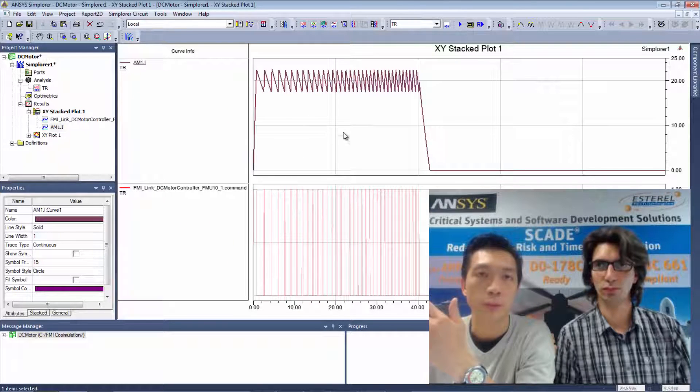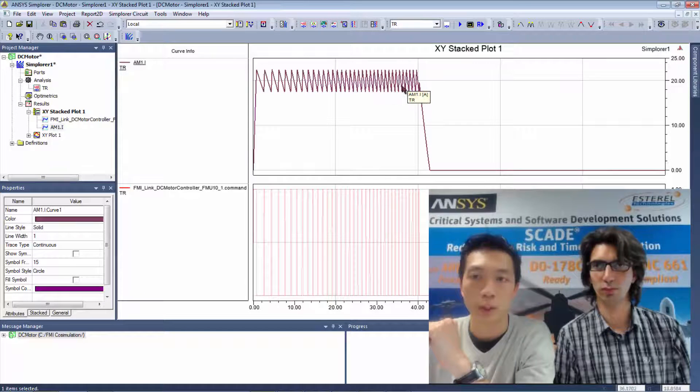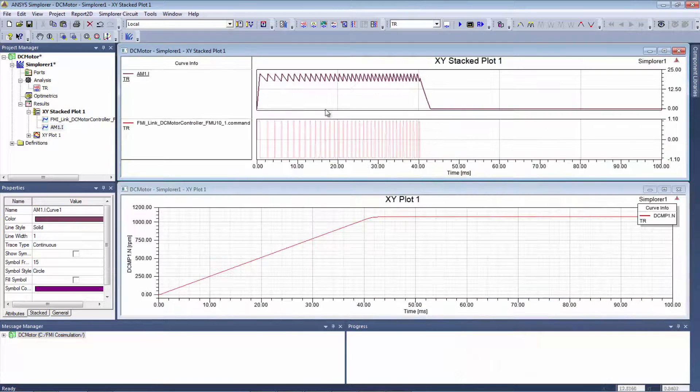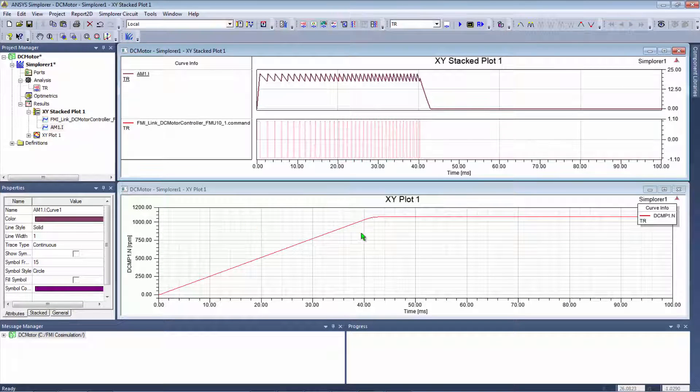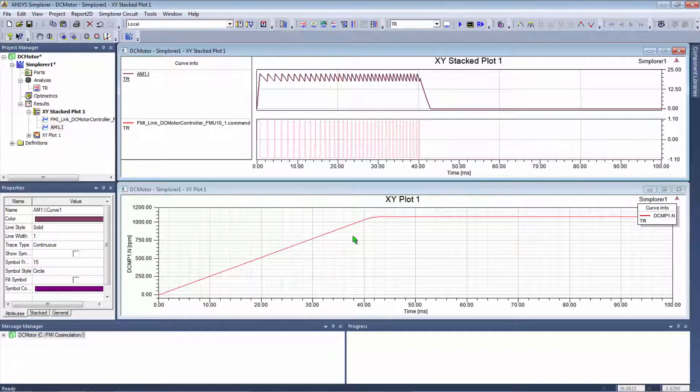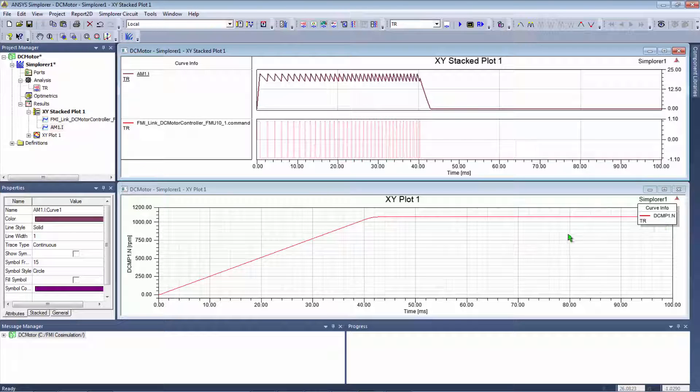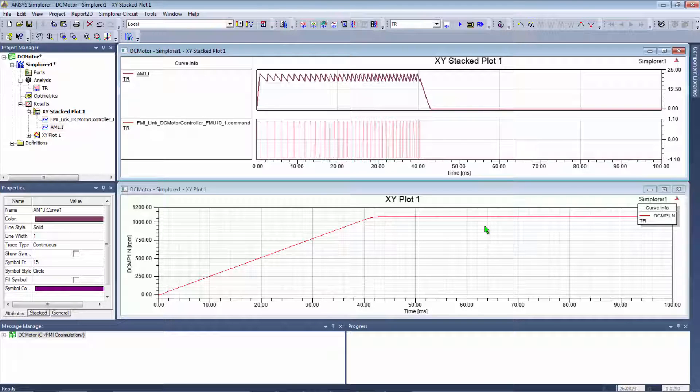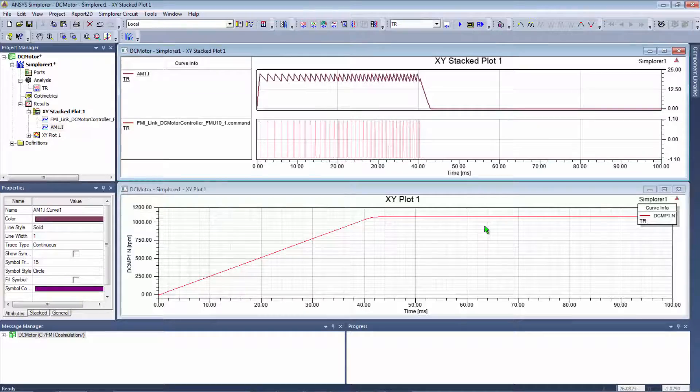And here we can see on the current waveform the hysteretic effect which is regulating the current here. And the regulation goes on until the regulation speed is reached. This is what you can observe here on the plot of the rotor speed of the machine. And this behavior is actually expected since we haven't put any load on the electrical machine.